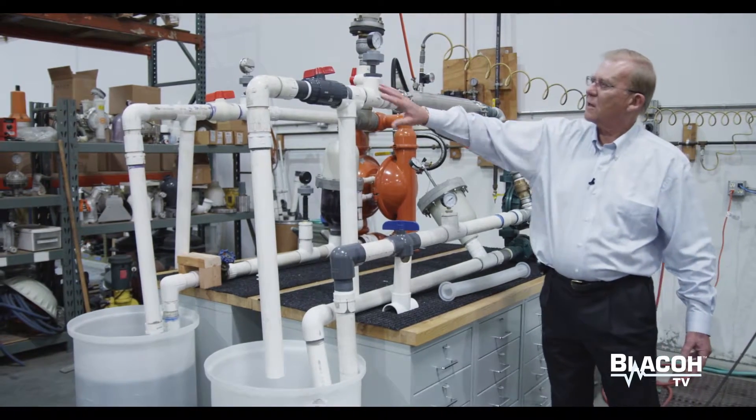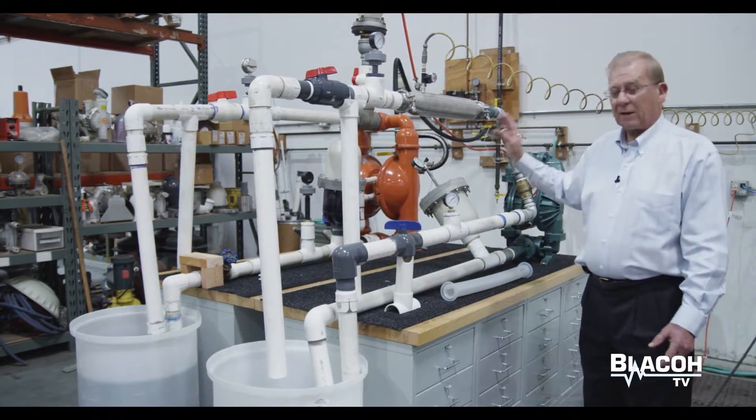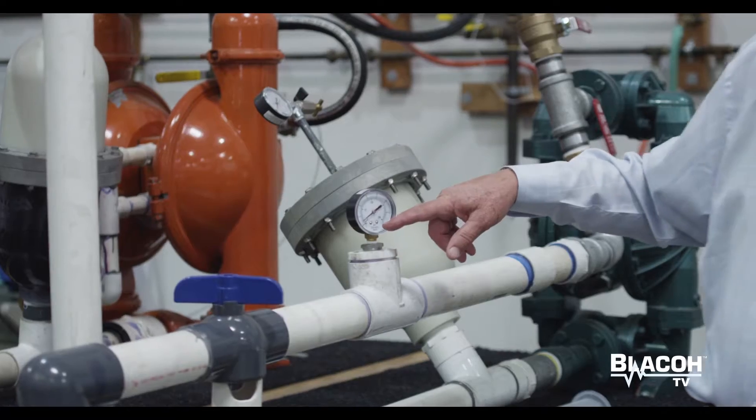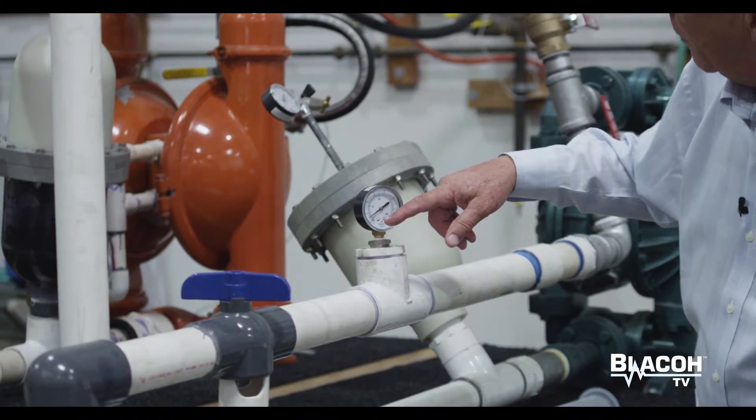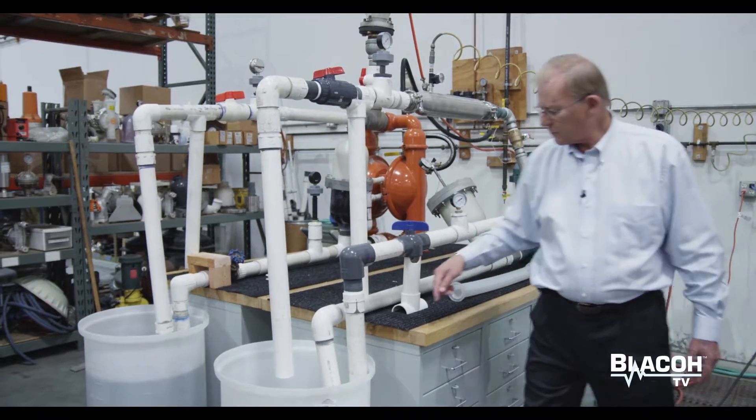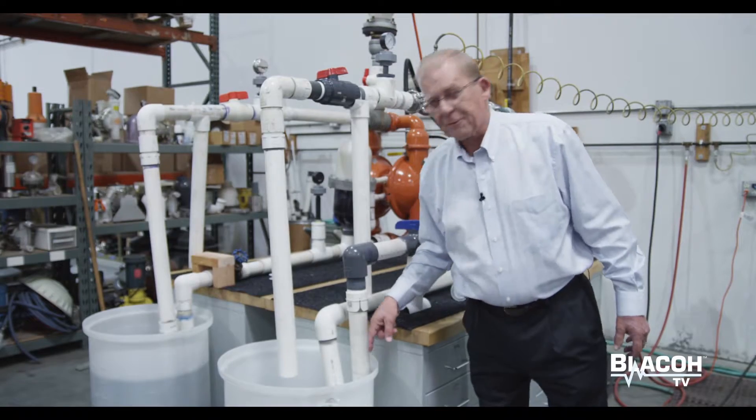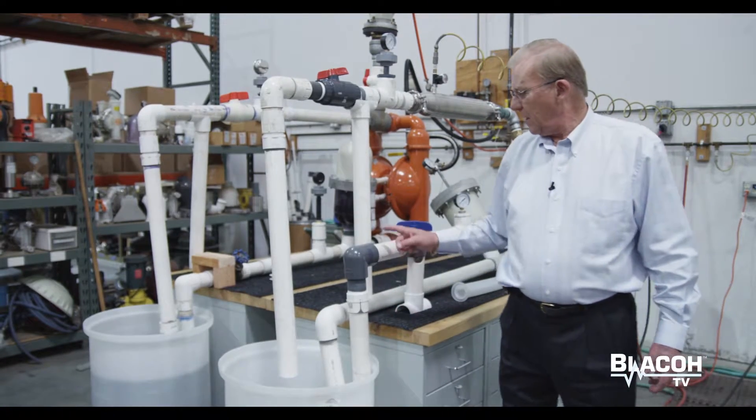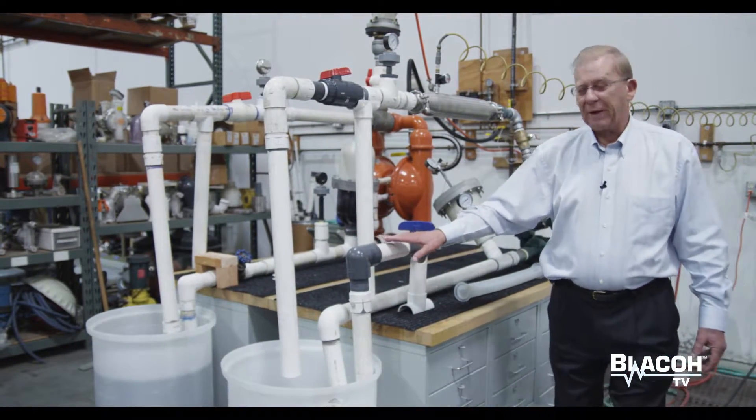So you'll still see some shaking due to mechanical vibration. Right now you can see the needle on the gauge is bouncing from zero up to about 25 psi. The flow is intermittent, starting and stopping, and the pipe is vibrating or jumping.